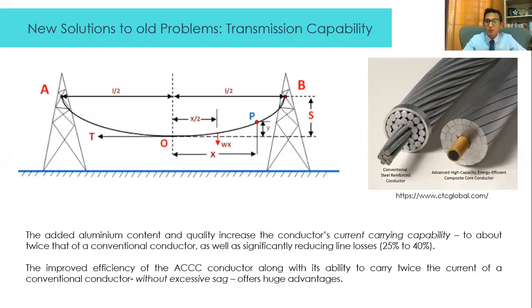It's been, I think, less than 10 years - it's a new technology which has been in place less than 10 years. So it's quite new, and you can double your transmission capability while decreasing your line losses by 25 to 40%, depending on how much current you're carrying. Isn't that interesting? You just replace the conductors and you double your transmission capacity while reducing your losses.